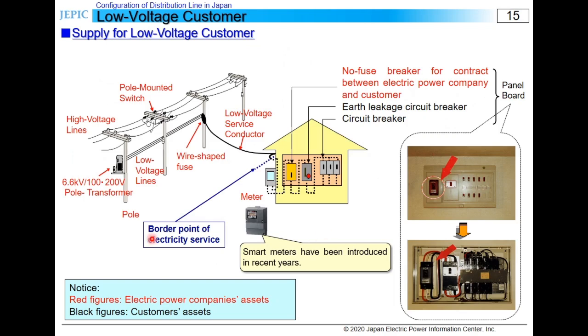This figure shows a standard facility of a general house. High voltage electricity is stepped down by transformer and supplied to customers through low voltage line and drop service line. A receiving point of drop service line is the border point of electricity service. A meter and contract breaker are normally installed on the customer side, but they are the electric company's possession. In recent years, smart meters have been installed, and they can be read and controlled remotely. We can remotely get meter data every 30 minutes, and the calculated every 30 minutes kilowatt-hour is offered to retailers.